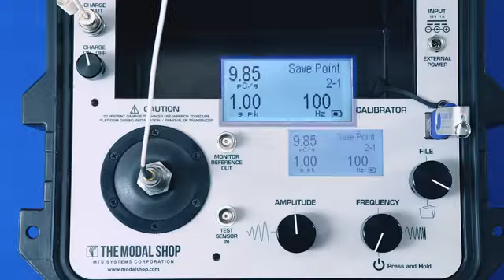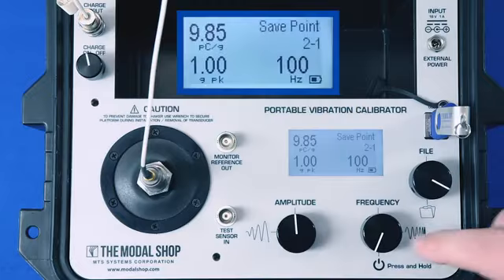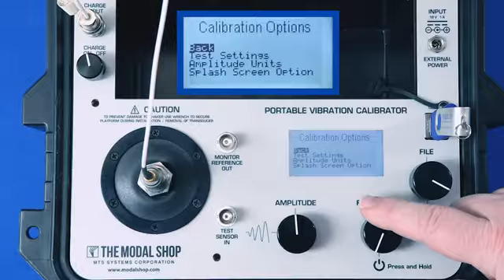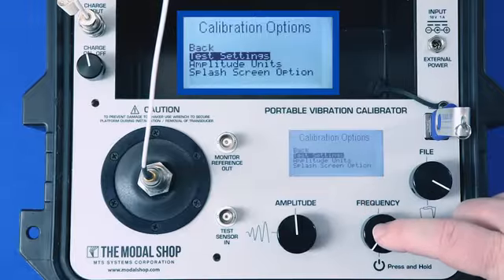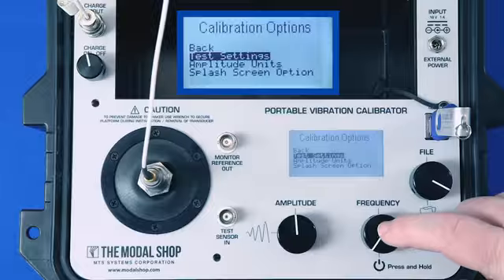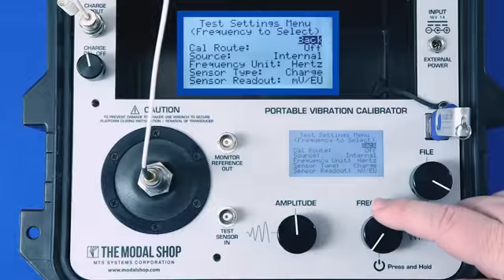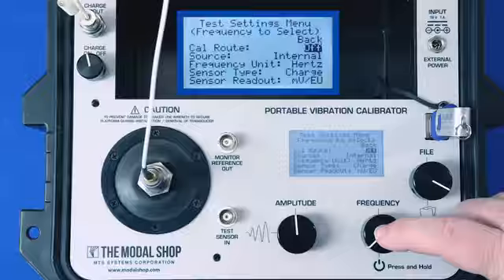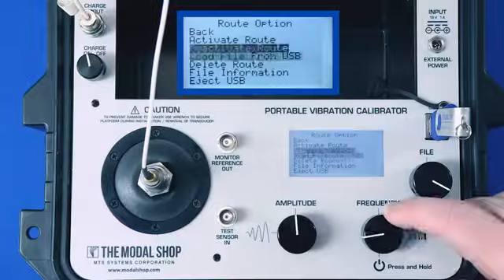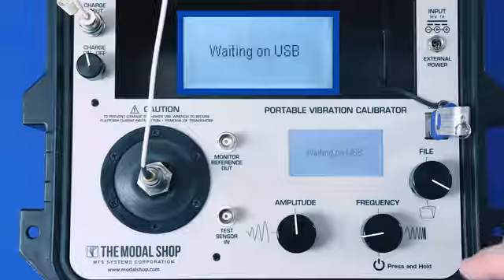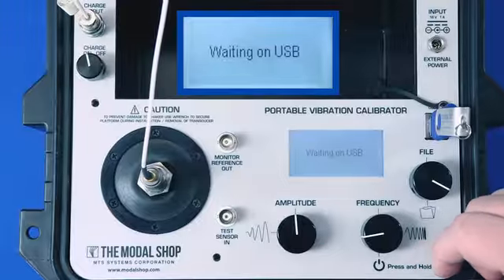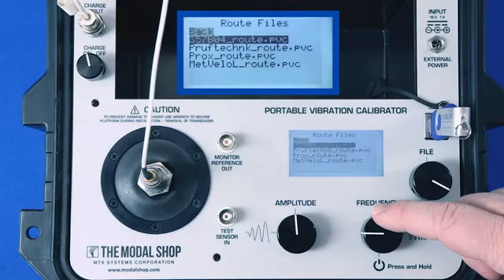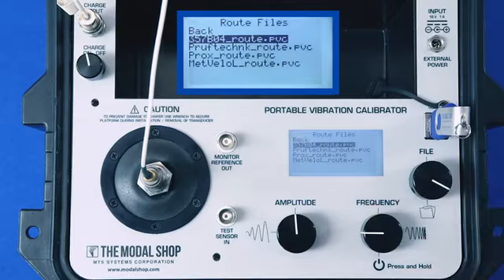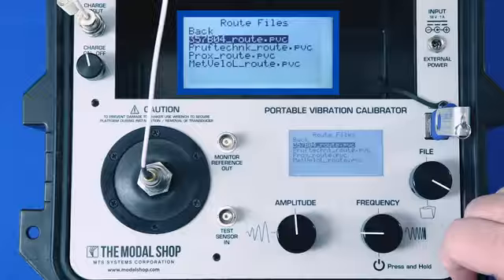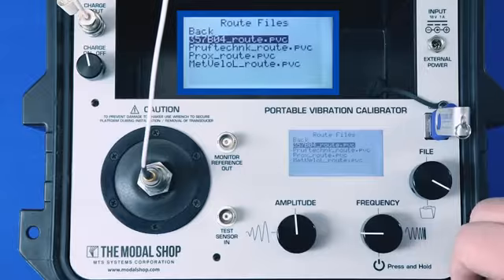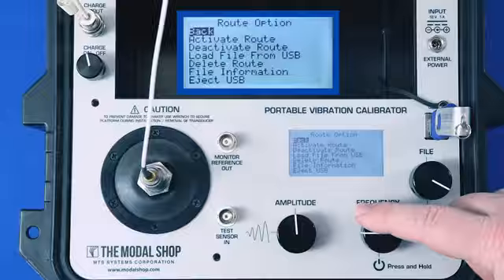The next step in calibrating the 357B04 is to load our pre-programmed step sine test with pass-fail notification and activate it. So I use the frequency dial to highlight the test settings. I go to the CalRoute function and I load a file from my USB that I've plugged into the top of the calibrator. The calibrator will read the USB and give me a list of available CalRoutes, or pre-programmed step sine tests. I'll choose the 357B04, and now I need to activate that test.